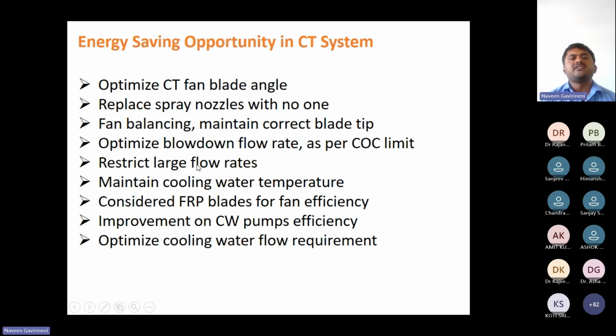Fan balancing, maintaining correct fan tips. Maintain COC. Restrict some flows, large flows. Maintain cooling water temperature. Consider FRP blades. Improve cooling water pump efficiency and optimize cooling water flow rate. These are all related to energy saving opportunities. You will not get this in any books, so be cautious about these energy saving opportunities.